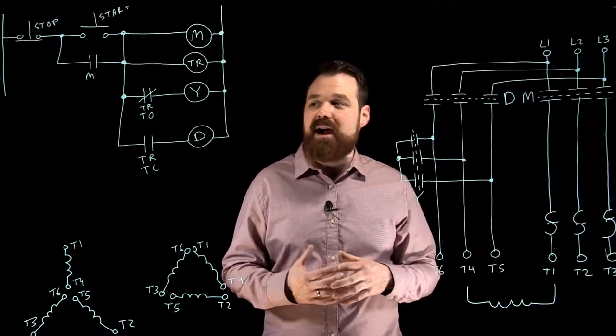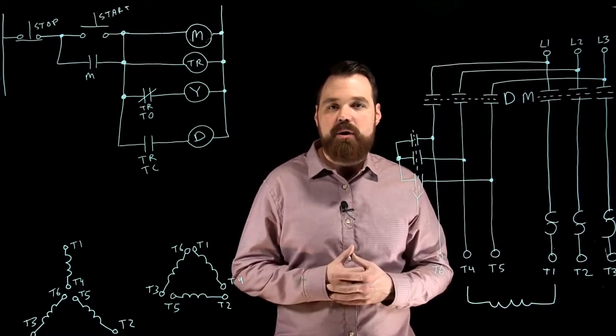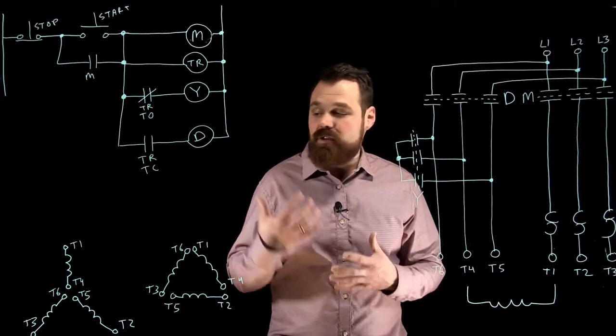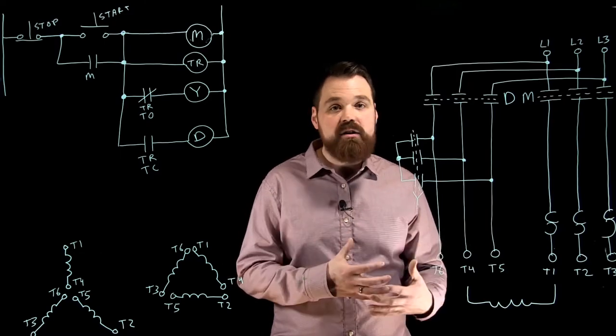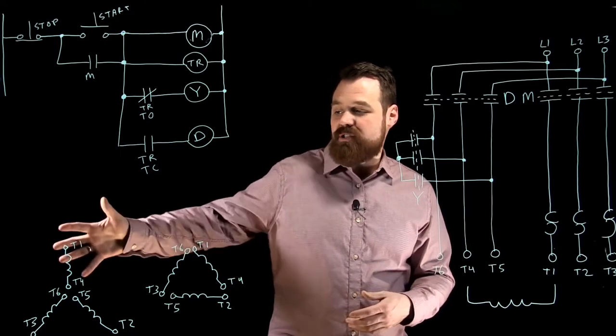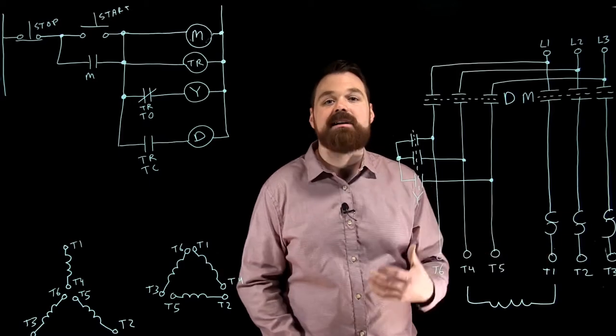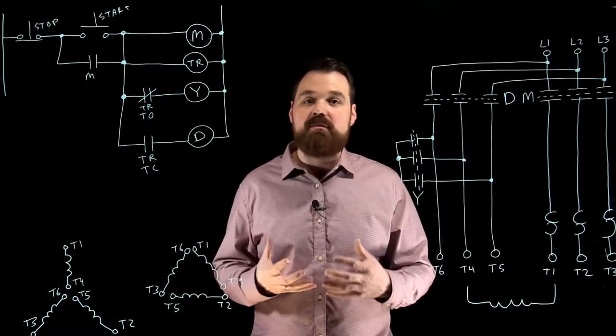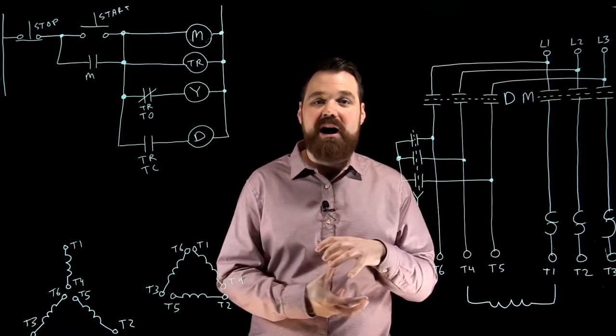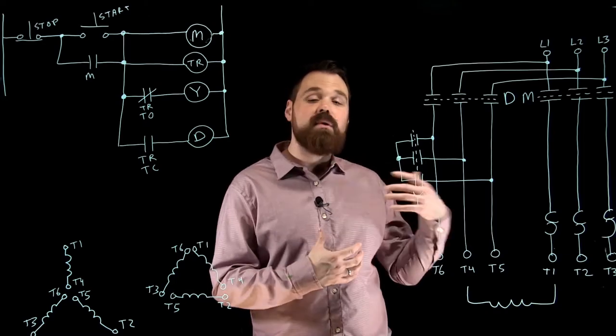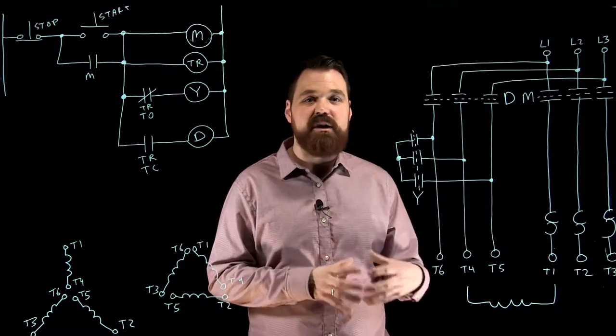The type I want to talk about right now is called a Y-delta starter. Basically with this, what we do is we take a six-lead single voltage motor, so it'll have T1 through T6 on it. What we're going to do is when we start the motor, we configure those windings in a Y formation, and then in order to run the motor, we switch them over into a delta formation.